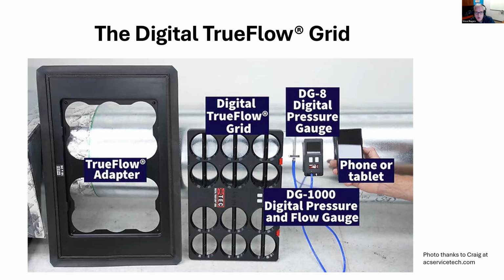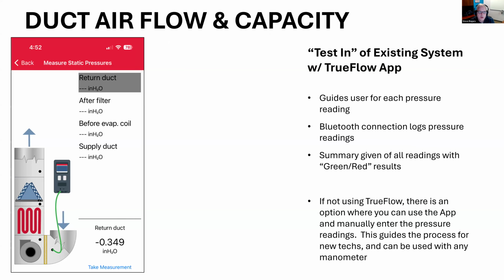So the way that it works is the app is going to guide the technician through the process of measuring static pressures first and then measuring airflows. So you can see they get an image of the type of system, and this image will change depending on whether I've got a filter that's in a filter slot, or whether it's a filter grill in the ceiling, whether I've got a furnace and cooling coil, or just an air handler with strip heat. So the user will choose those options so that they'll get an image of what they need to measure.